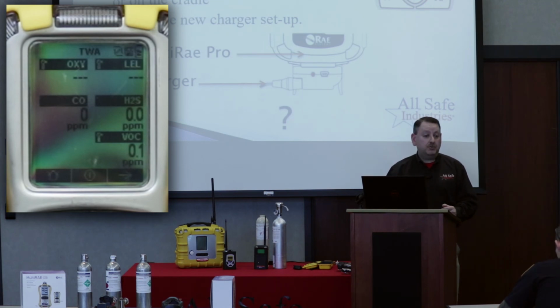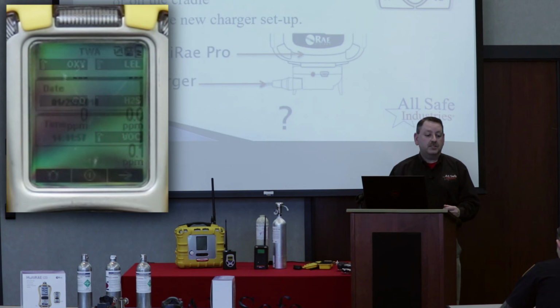If it exceeds what OSHA says you should be exposed to in an 8-hour period, you'll get the time-weighted average alarm. Side note that your short-term exposure limit and your time-weighted average alarms only register on the toxic sensors. No such thing as a time-weighted or a short-term exposure to oxygen or to flammable gas, because that is not a normal gas to be exposed to, okay? Go ahead and hit your arrow button again. What's the next screen say?